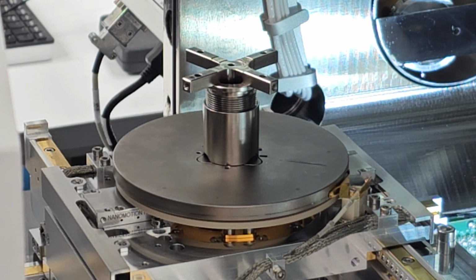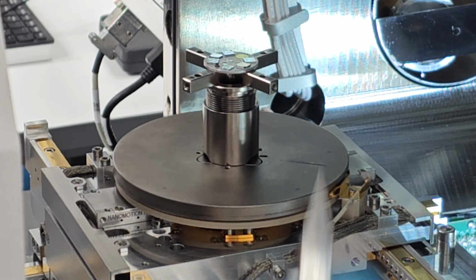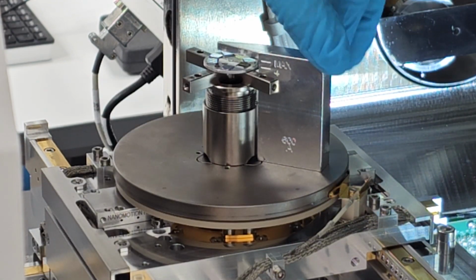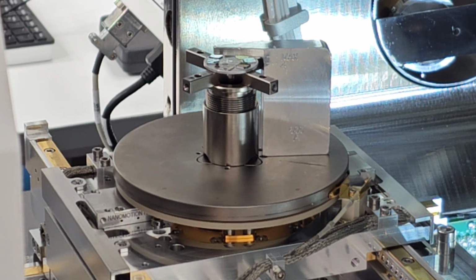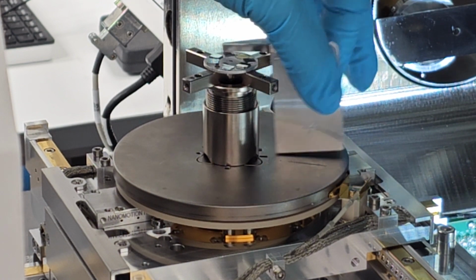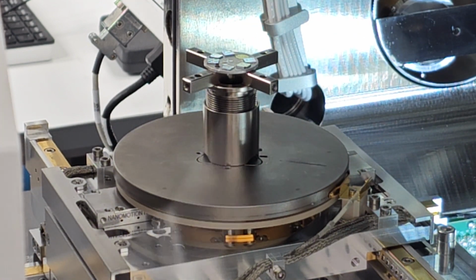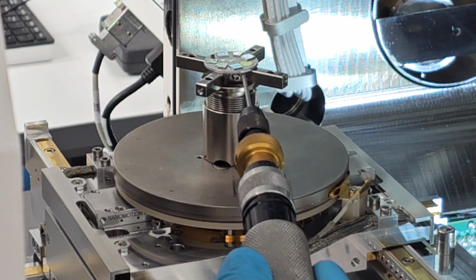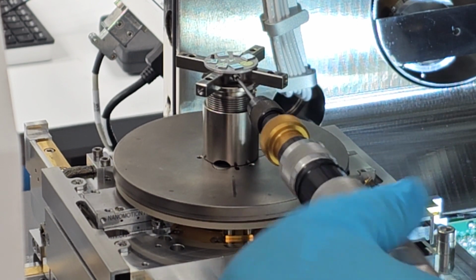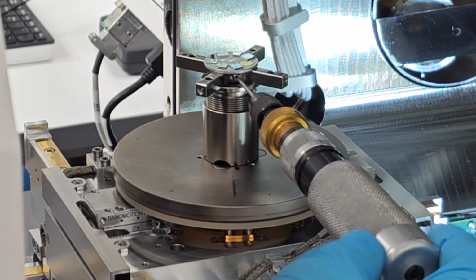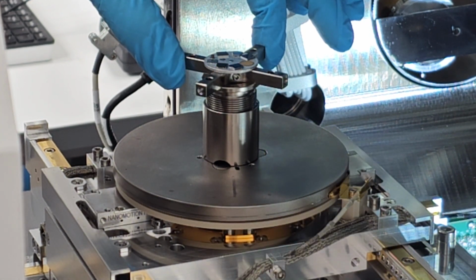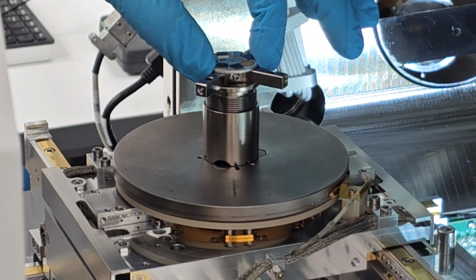see, nice and tight, and now I can put the sample back in and measure my height. And I am above the 4 mark, but below the max. This is where I want the top of my sample to be. So now all I have to do is take the torque wrench, find where the set screw is right here, and tighten it down until the torque wrench clicks. Now not only is the sample holder nice and solid, but so is the sample itself.